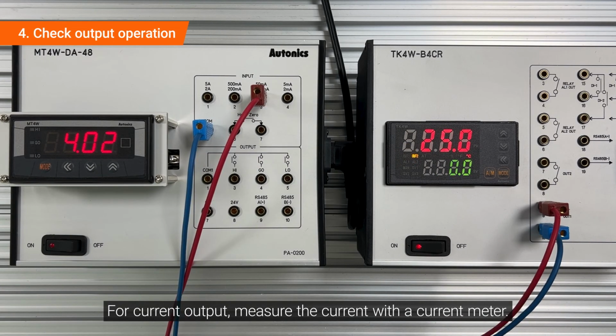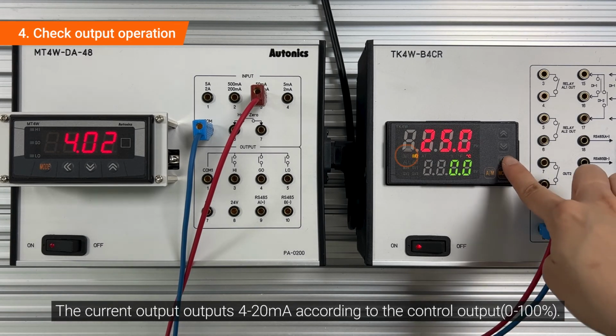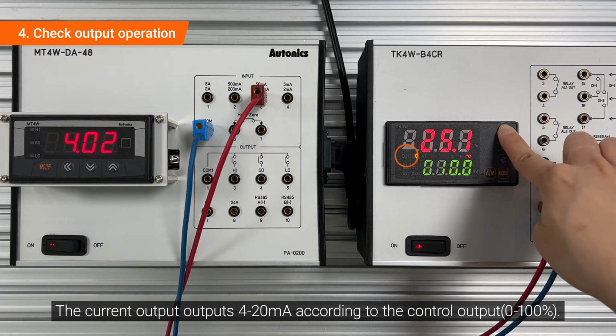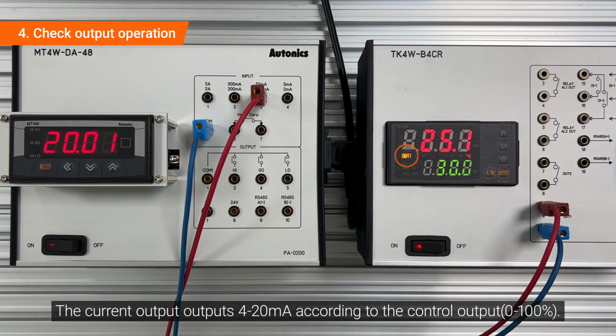For current output, measure the current with a current meter. The current output outputs 4 to 20 mA according to the control output.